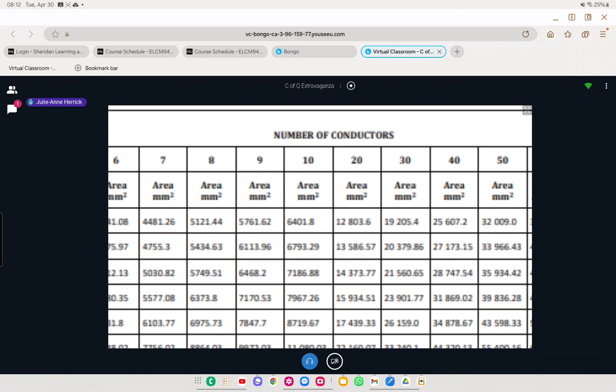We're all familiar with table 6A for conduit fill. I just want to remind everybody that when you're looking at the top, please pay attention to whether it says jacketed or unjacketed and what the voltage is. Table 6A is unjacketed 600 volts, 6B is jacketed 600 volts, 6C is unjacketed 1000 volts, and 6D is jacketed 1000 volts. You don't want to get the wrong answer just because you weren't paying attention.